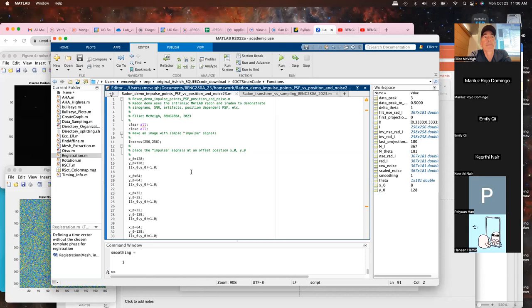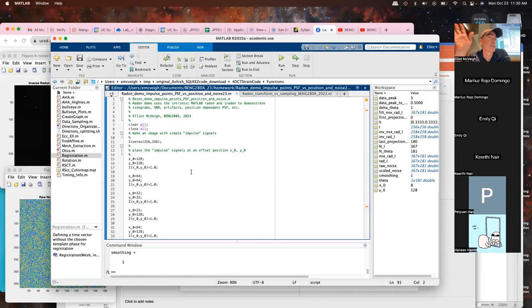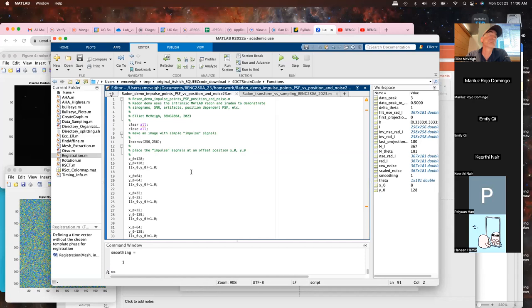Another question: can you take more angles, average them, and get a better picture? Yes — you can take more angles and it's just like averaging. The noise goes down, but after a while you're not gaining new information, just averaging. If something is moving, you'll want to limit the acquisition time window or you'll start getting motion artifacts.